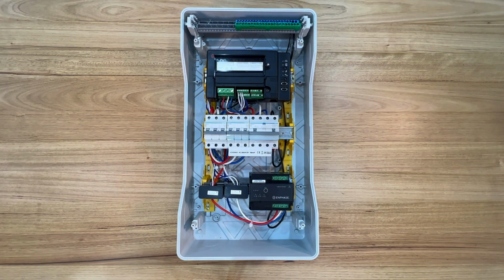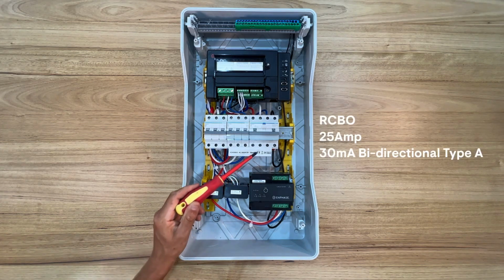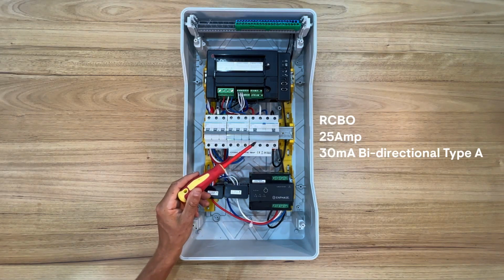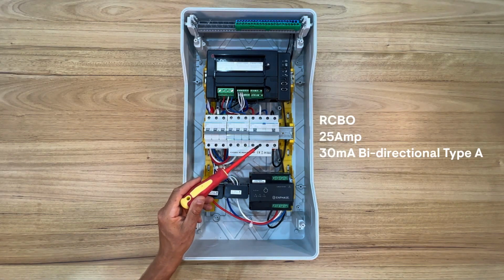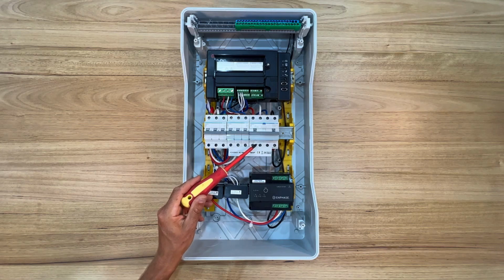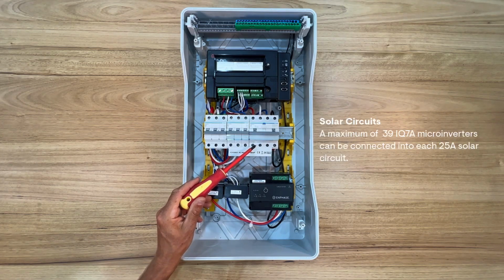An IQ gateway communicates by AC power line through the AC circuit wiring to IQ relays and microinverters in an installation. This example uses a 25 amp RCBO, or you can also use a multi-phase 25 amp circuit breaker for each of the AC solar circuits.